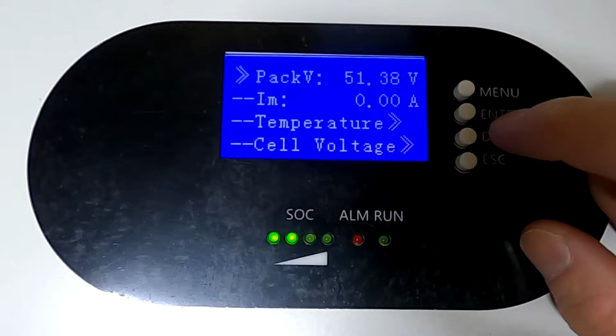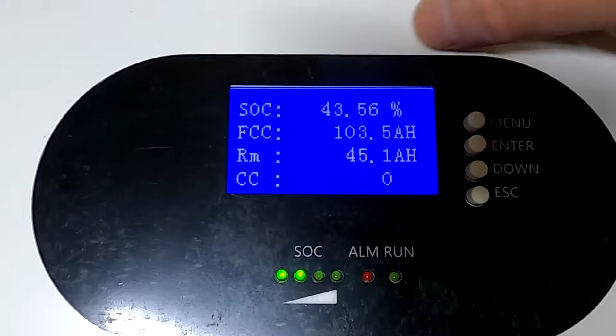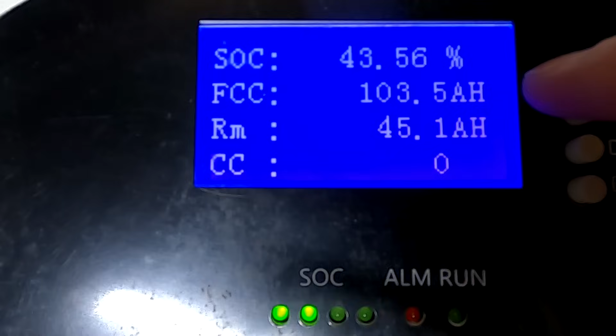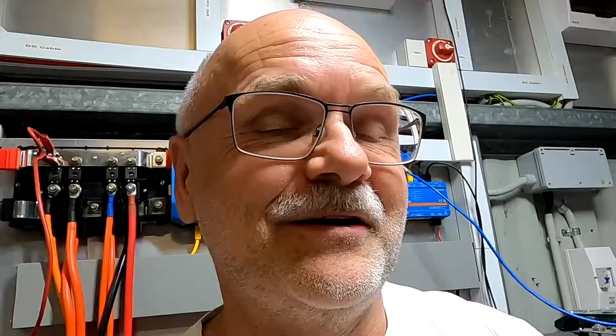Gives us 51.38 pack voltage. We go all the way down, and have a look, we're at 43.56% state of charge. The rated capacity is 103.5 ampere hours, remaining 45 ampere hours.